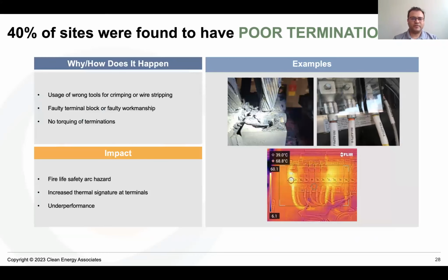Yeah, we have found approximately 40% of the sites having poor terminations. And by poor terminations, I mean cut strands, strands that are loose, or the cables not torqued at all, just readily coming off the termination. This is a major issue. And the picture on the top left that you see is a picture after a thermal event due to a poor termination on one of the AC switchboards that we have seen over here.